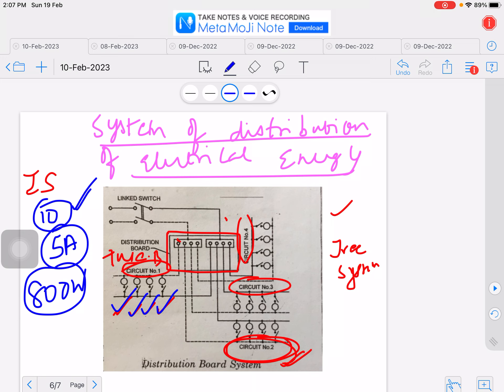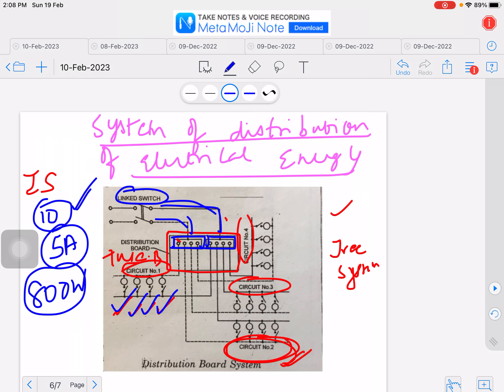In this connection you can see two copper strip wires known as the bus bar — these two copper strips are feeding the circuits. The distribution board can be mounted on a hardwood or metal case. It is connected through the linked switch, which allows you to switch the whole supply on or off with one throw. This is also called a DPST — double pole single throw — where by a single throw both poles are controlled. A fuse is inserted in the phase wire of each circuit.